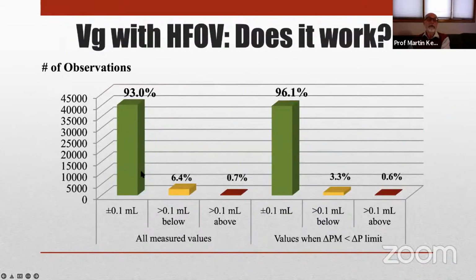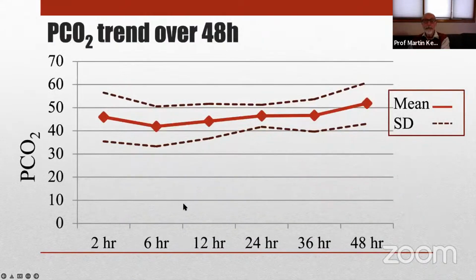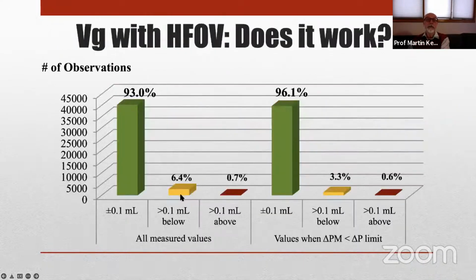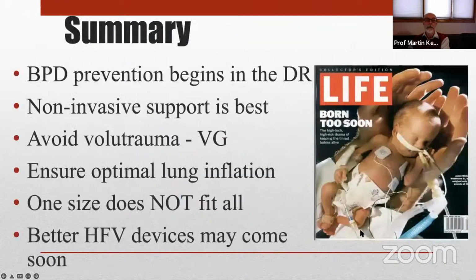We looked at thousands of cycles, and 93% of the time in the raw data, the measured tidal volume was within 0.1 ml of target. 6.4% of the time it was a little bit above or below target. And the reason for that in a significant number was that the clinicians failed to adjust the amplitude limit. So the machine couldn't do what it was trying to do. When we eliminated the user error related tidal volumes, the percentage went up to 96%. So it really works incredibly well.